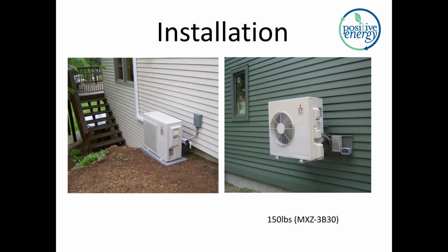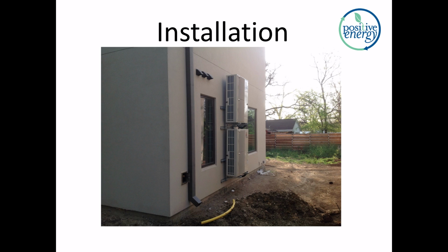Here are some examples of installation. They're light and compact. They can be wall mounted. They can also sit in the standard way, on a pad. You can put the refrigerant lines in the wall, or you can run them through those plastic conduits. Here's another application where we have 2 of the, I believe those are Mitsubishi S-Series outdoor units, both wall-mounted, one above the other. There might be some considerations about when the upper unit defrosts, it might dump some water onto the lower one, but that shouldn't really be a performance issue because these units are outside and water landing on them is not a problem. Extremely quiet. There are definitely requirements as to how you're allowed to stack these and align them, and you do need to allow for good airflow, but those requirements are not stringent. It's typically 3 to 5 feet away before you can put an obstacle.